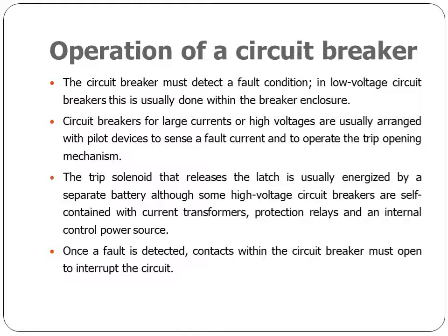Operation of a circuit breaker. The circuit breaker must detect a fault condition. In low voltage circuit breakers, that is usually done within the breaker enclosure. Circuit breakers for large currents or high voltages are usually arranged with pilot devices to sense a fault current and to operate the trip opening mechanism. The trip solenoid that releases the latch is usually energized by a separate battery, although some high voltage circuit breakers are self-contained with current transformers, protection relays, and an internal control power source.